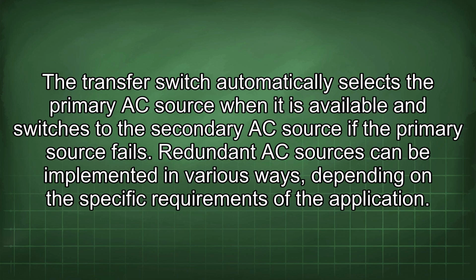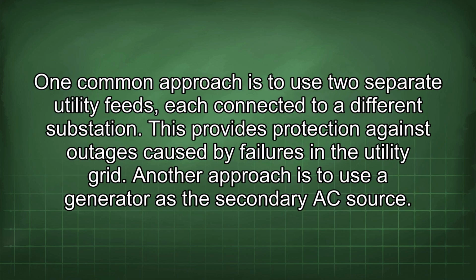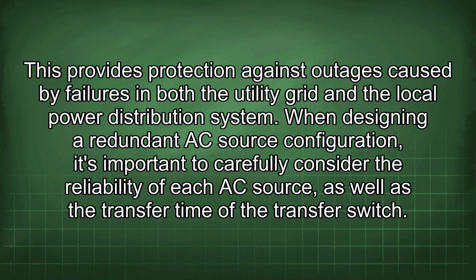Redundant AC sources can be implemented in various ways, depending on the specific requirements of the application. One common approach is to use 2 separate utility feeds, each connected to a different substation. This provides protection against outages caused by failures in the utility grid. Another approach is to use a generator as the secondary AC source. This provides protection against outages caused by failures in both the utility grid and the local power distribution system.